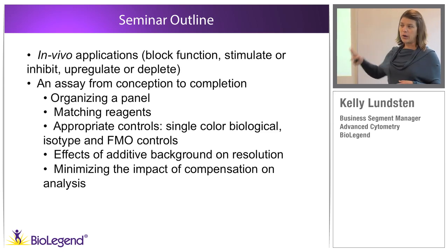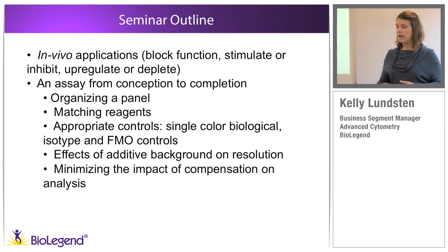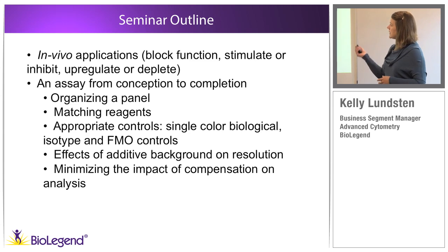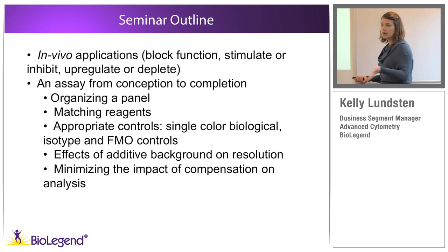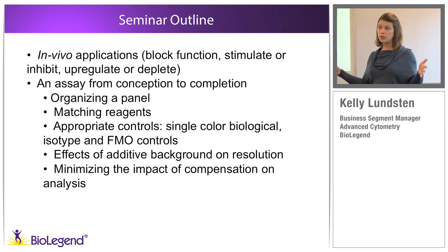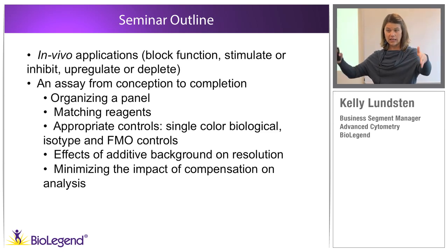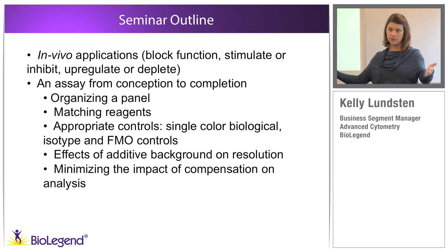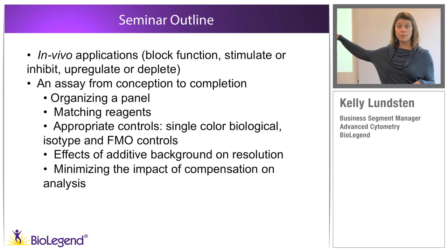We're going to talk about the process to ensure that when you get to that point, you have the cleanest set of data possible to make your analysis internally consistent, reproducible, and clear. We'll discuss all the appropriate controls involved, including single color biological controls so you can appropriately assess the voltage range of each PMT and keep the same voltages for the majority of your experiment.